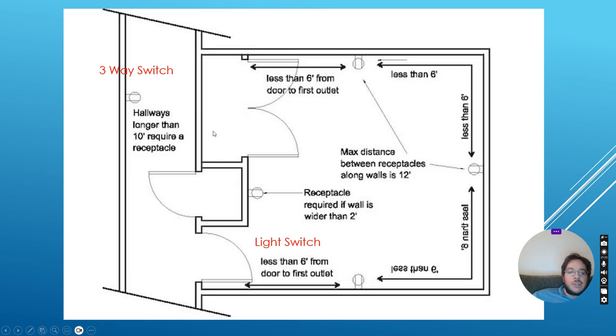But this rule doesn't apply inside a closet or a storage room or a laundry room, that kind of thing. But I need a receptacle in any hallway longer than 10 feet. And I need a light switch next to every door.